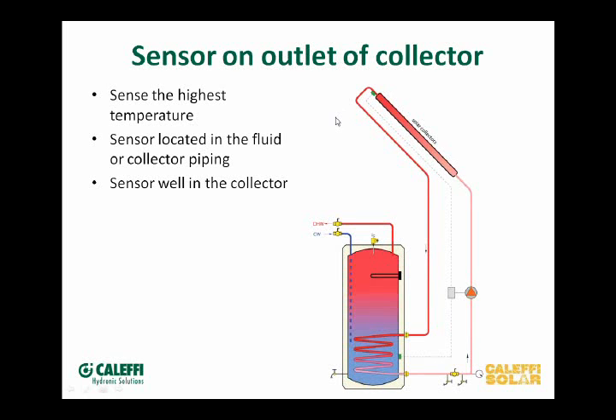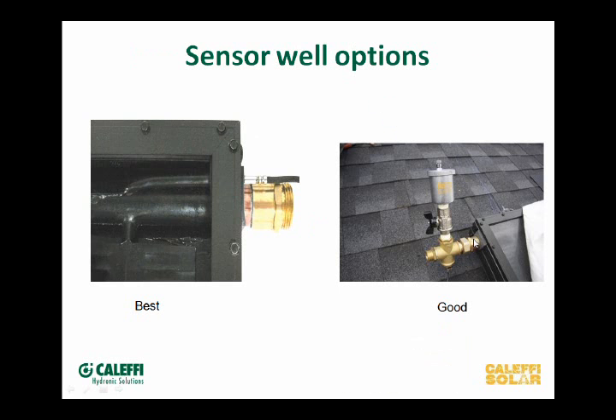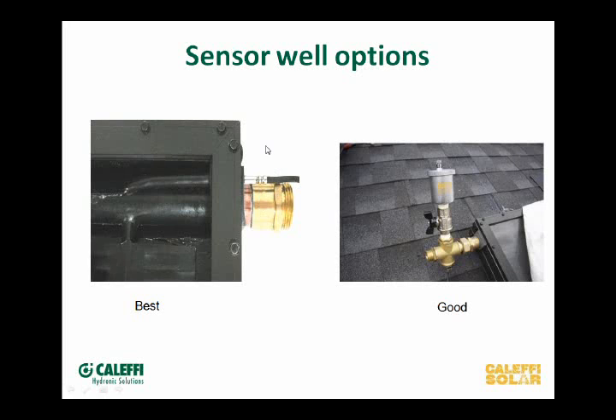We've got cross fittings available — they come with our kit or you can buy them individually — in many different sizes for different thread types, including 15mm for evacuated tube headers. The cross fitting has a well right in it, which gets the sensor at the high point on the collector and actually in the fluid. Instead of just strapping it on the outside of the pipe with a hose clamp and insulation, now we've got it in the fluid so it reads temperature better.